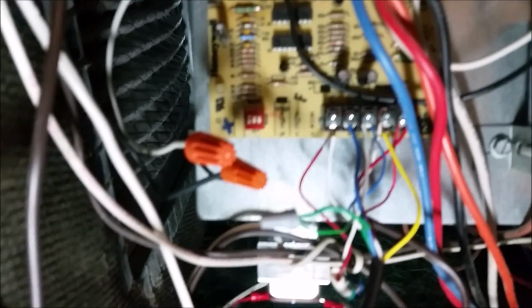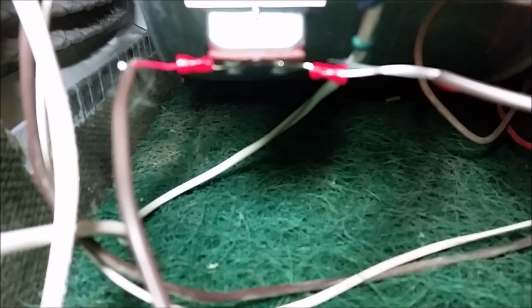The Aprilaire ships with a transformer, which converts the 110 volt down to 24 and 10. The 24 volt on mine is on the right and the 10 is on the left. There's a part in the back you can't see, screwed into a hole, with a black and white wire coming out of it, and that's what powers the transformer.